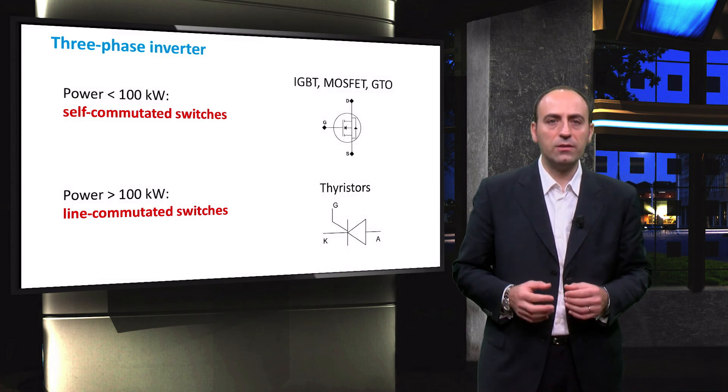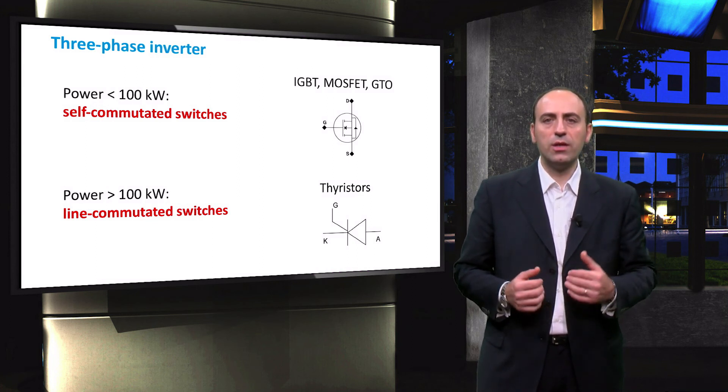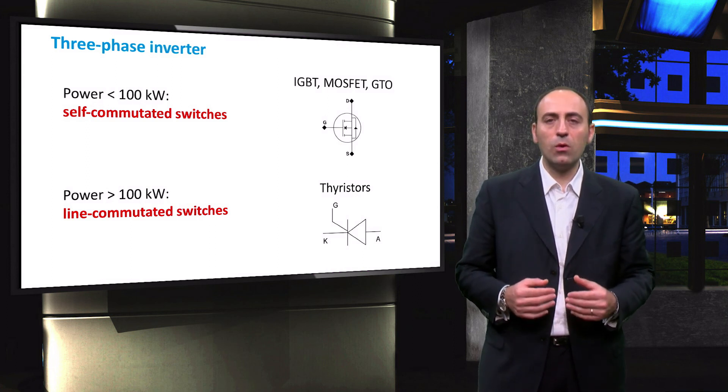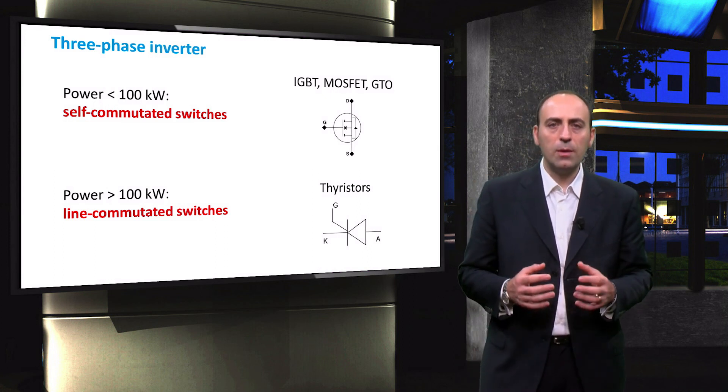When it comes to power higher than 100 kW, line-commutated semiconductor devices, such as thyristors, are chosen. Unlike self-commutated devices, thyristors need an input signal, usually retrieved from the grid, to start conducting. This option is typically employed for high voltage DC and high voltage AC applications.